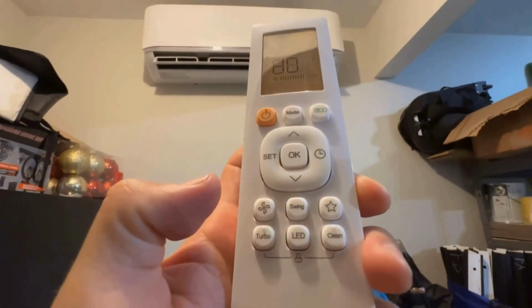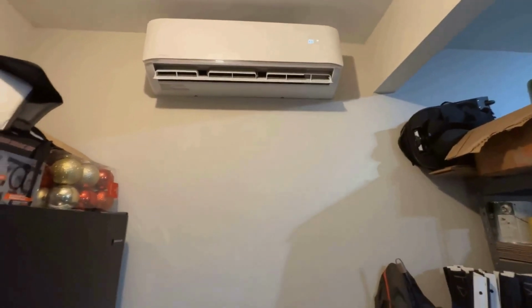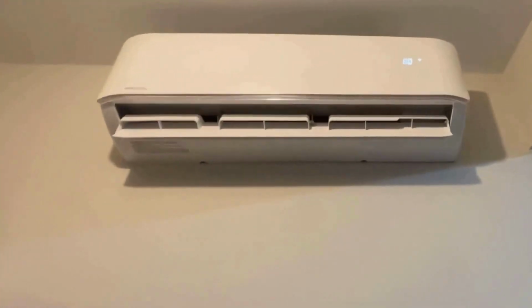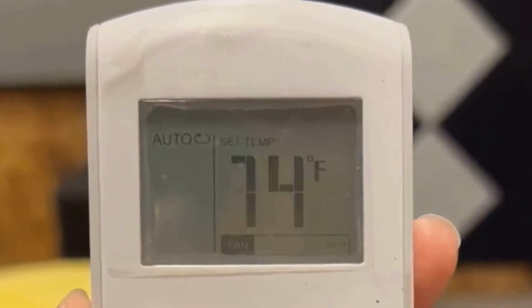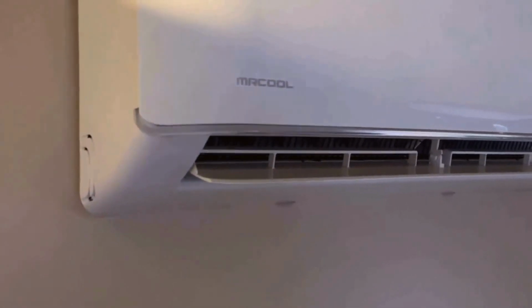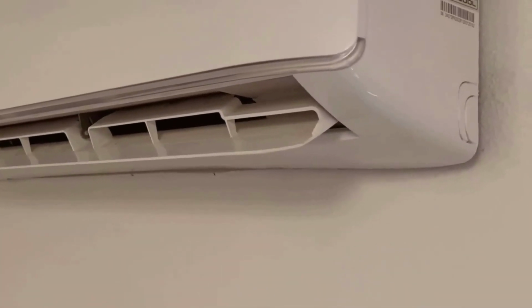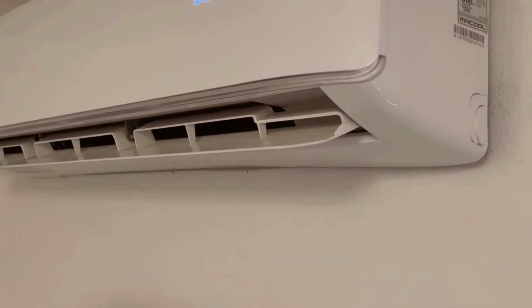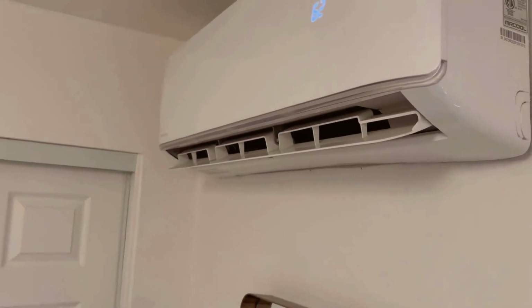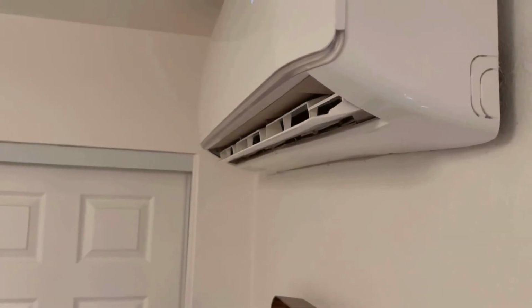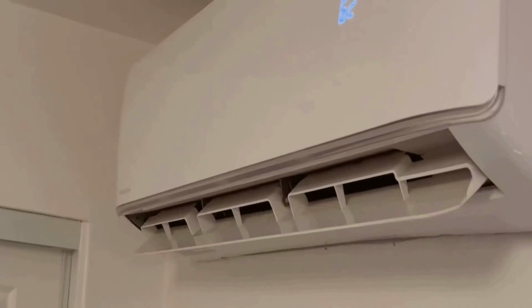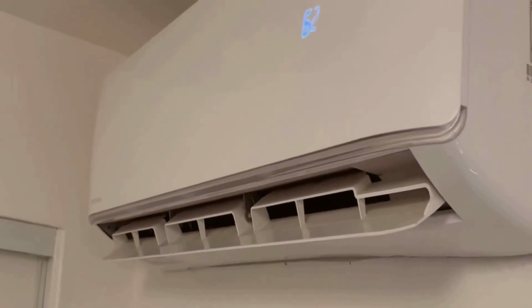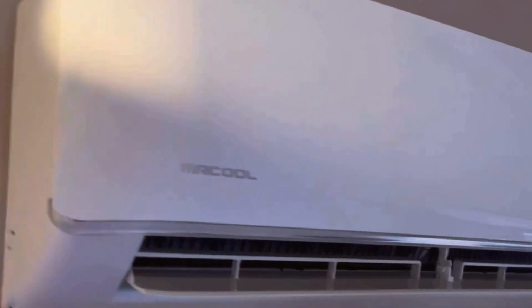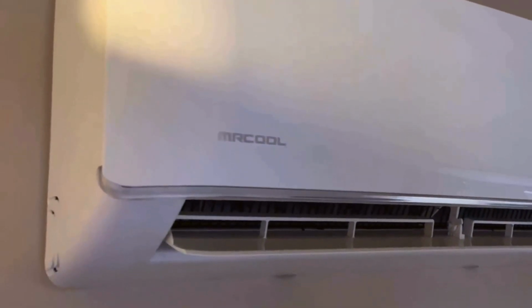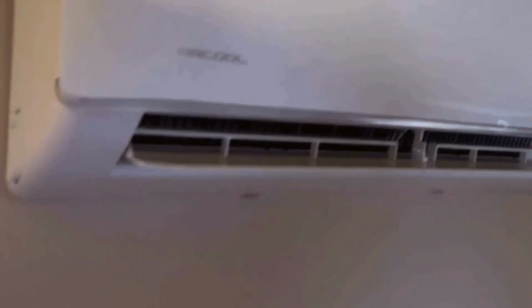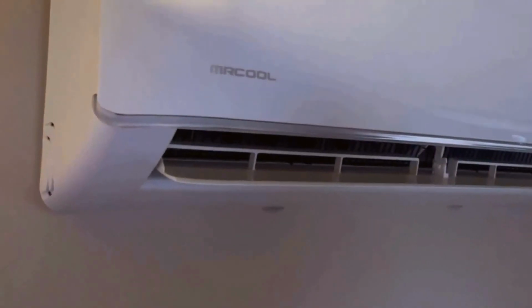The sizing guidance on the product page matched my application, but I'll add this. Cooling a number on paper and cooling a space you live in can feel different. If you're on the fence between sizes, look at your insulation, sun exposure, and ceiling height. A 24K unit in a well-insulated 900 to 1,000 square foot space is a great fit. In a poorly insulated shop with bay doors opening all day, you'll still get improvement, but don't expect meat locker cold. Heat pumps do a lot of things well, but beating pure conduction losses through thin walls isn't one of them.